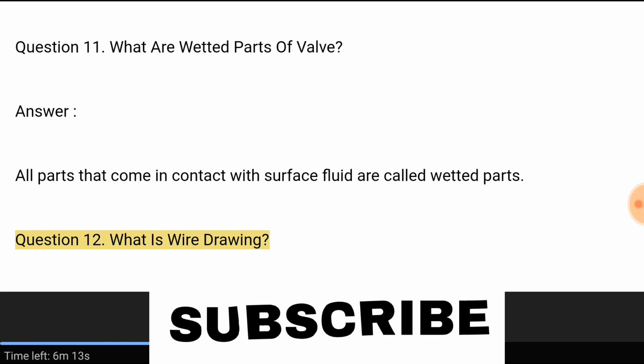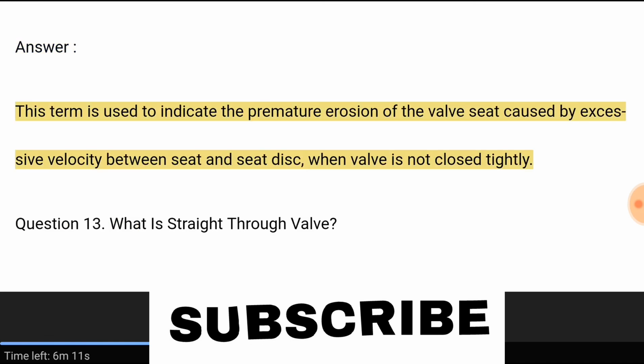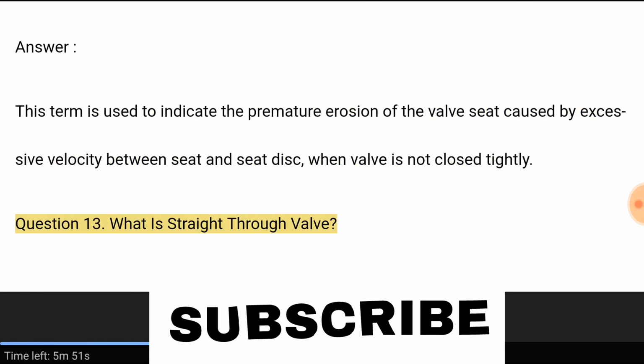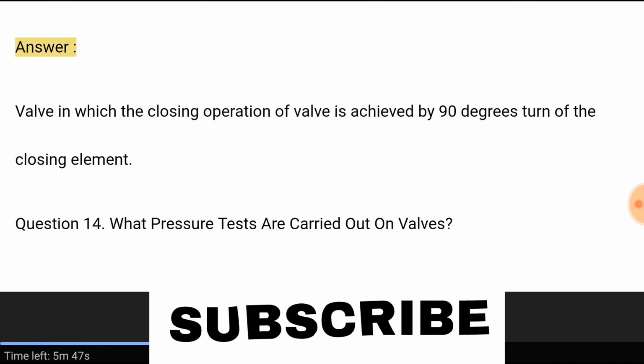Question 12. What is wire drawing? Answer. This term is used to indicate the premature erosion of the valve seat caused by excessive velocity between seat and seat disc when the valve is not closed tightly. Question 13. What is a straight-through valve? Answer. A valve in which the closing operation is achieved by a 90 degree turn of the closing element.